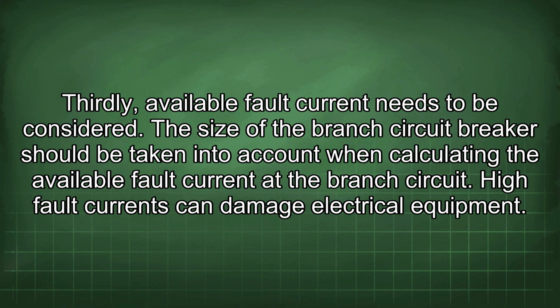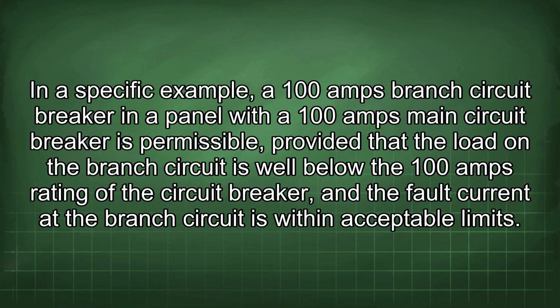Thirdly, available fault current needs to be considered. The size of the branch circuit breaker should be taken into account when calculating the available fault current at the branch circuit. High fault currents can damage electrical equipment. In a specific example, a 100 amps branch circuit breaker in a panel with a 100 amps main circuit breaker is permissible, provided that the load on the branch circuit is well below the 100 amps rating of the circuit breaker, and the fault current at the branch circuit is within acceptable limits.